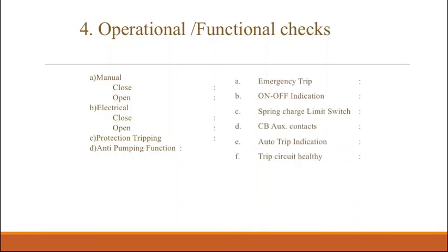Here I have taken the minimum operational and functional checks, and these may increase depending upon the circuit or the scheme. These are the minimum basic operational and functional checks. The first one is manual close and manual open, electrical close and electrical open. Either we can consider remote close and remote open, SCADA close and SCADA open, protection tripping.